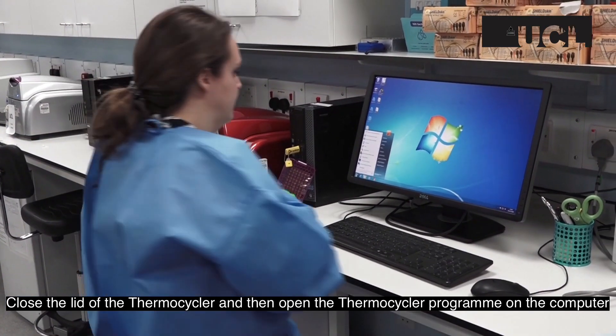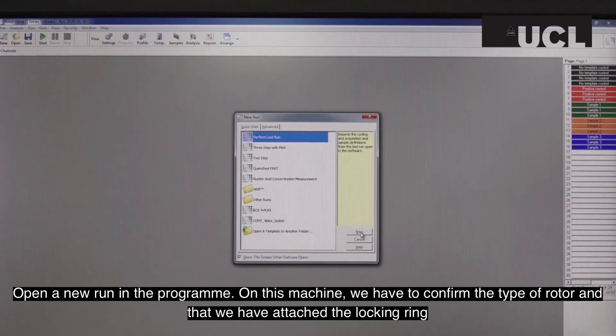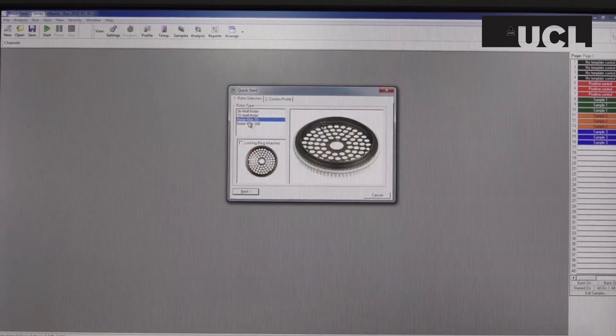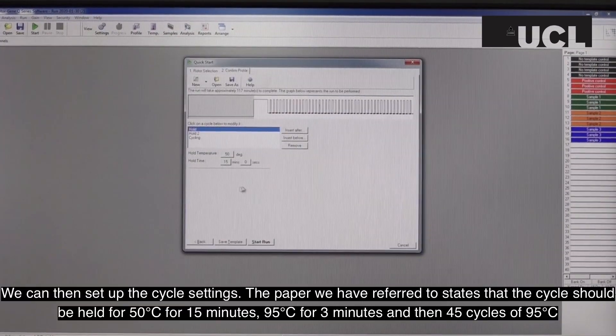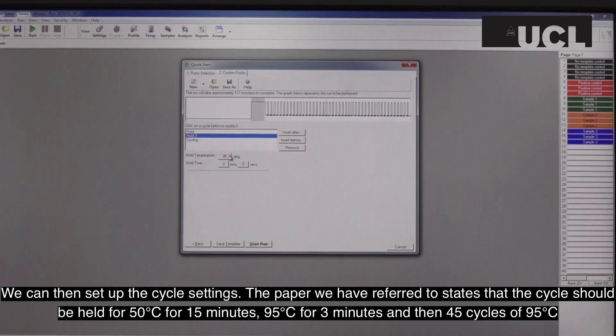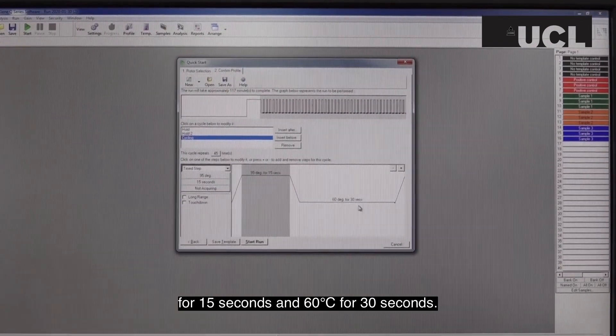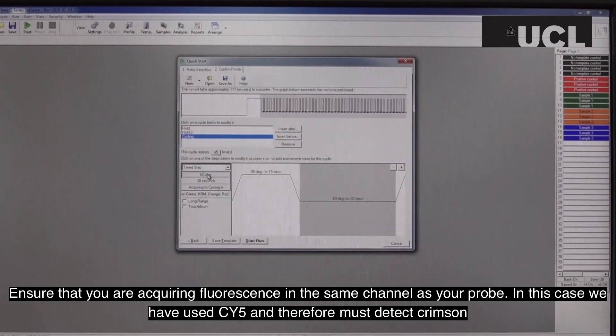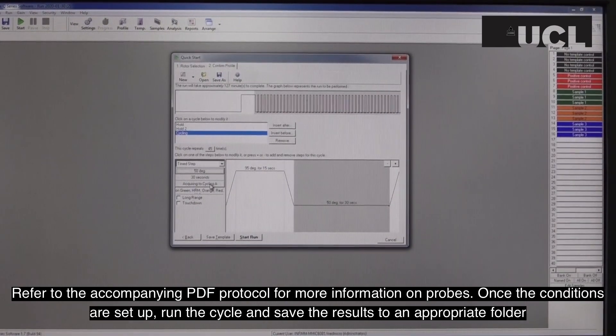Close the lid of the thermocycler and then open the thermocycler program on the computer. Open a new run in the program. On this machine, we have to confirm the type of rotor and that we have attached the locking ring. We can then set up the cycle settings. The paper we have referred to states that the cycle should be held at 50 degrees for 15 minutes, 95 degrees for 3 minutes, and then 45 cycles of 95 degrees for 15 seconds and 60 degrees for 30 seconds. Ensure that you are acquiring fluorescence in the same channel as your probe — in this case, we have used CY5 and therefore must detect crimson. Once the conditions are set up, run the cycle and save the results to an appropriate folder. You can then label each of your samples in the program.